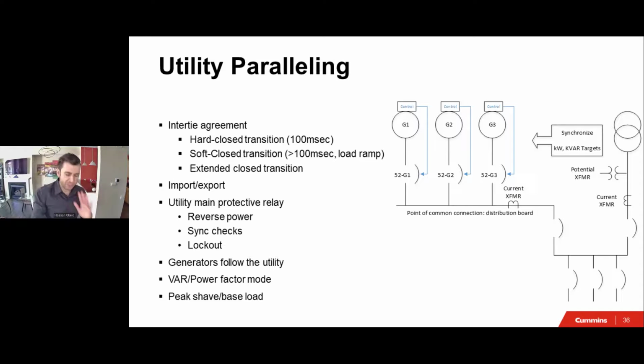Close transition with the utility, especially extended paralleling. If you have an extended paralleling application or a close transition with the utility, typically there's a hard close transition, which is less than 100 millisecond. There is a soft close, which is just long enough, more than 100 millisecond, but really there's no set time. It could be half a second, a little bit more, a little bit less, just long enough to take the loads from one source into another.